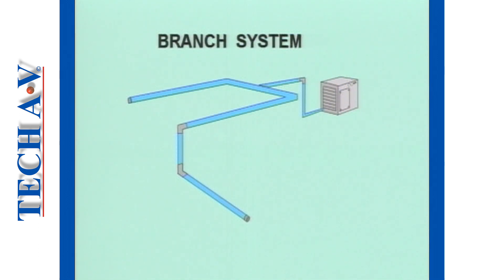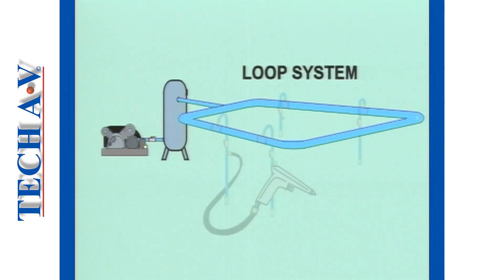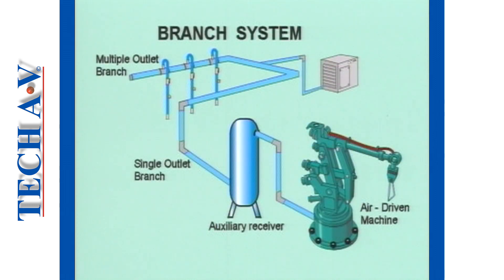There are basically two ways in which an air main can be set out: a branch system, where the main splits off in various directions and terminates at the end of a branch; or it may be set out in a loop system, where the air flow can circulate. Loop systems are best suited to applications where several working devices, such as power tools, are in use. A branch line is usually used to supply air to a single heavy consumption device.